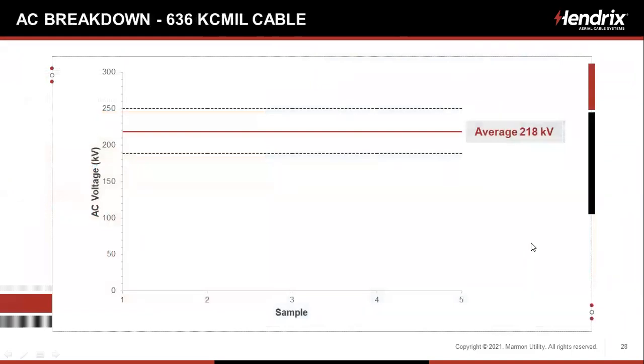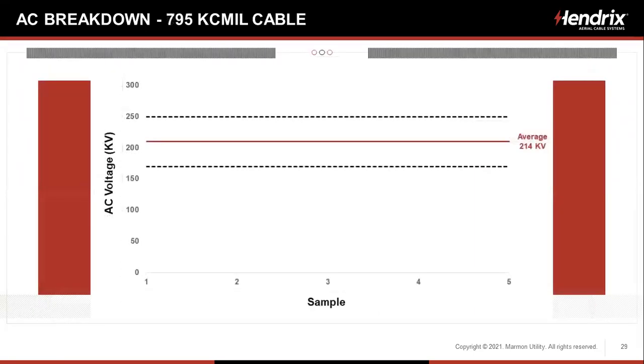So the AC breakdown, and we had a couple of samples here. We did a 636 and a 795. We knew what the AC breakdown was going to be because we know the AC breakdown of high density polyethylene exactly. But anyway, we had to do the test. So we got an average of 218 kV for 5 samples, which is about 5.5 per unit for line and neutral voltage. So that's pretty darn satisfactory for AC breakdown. We took the other sample, the 795, we got the same data, 214 kV, again about 5.5 per unit for the line and neutral voltage. So that is also very satisfying.